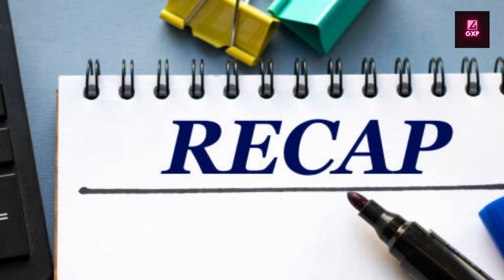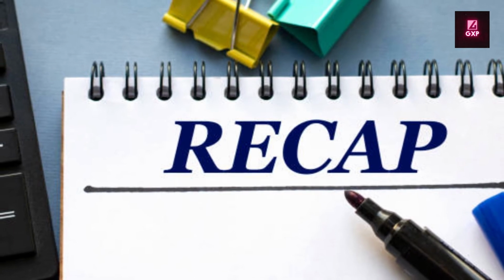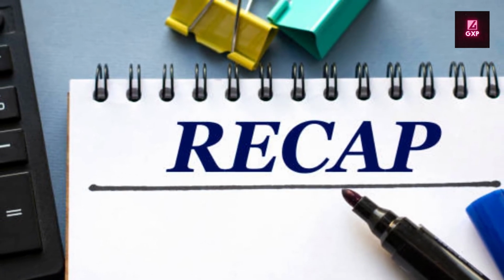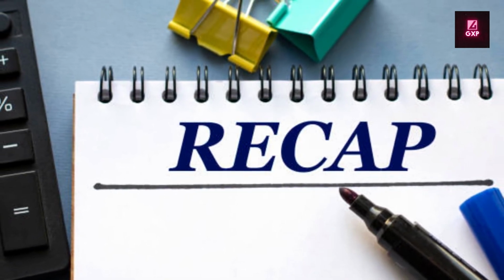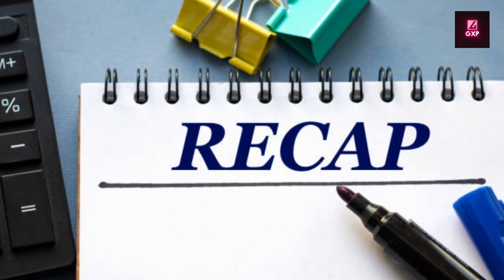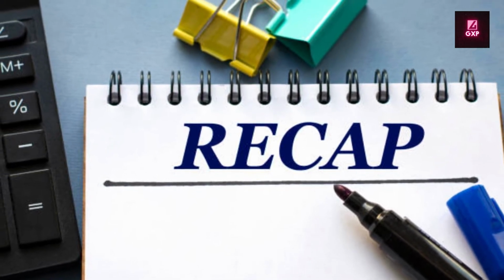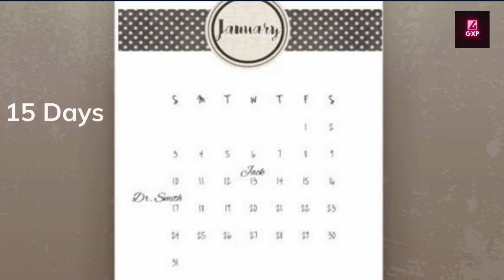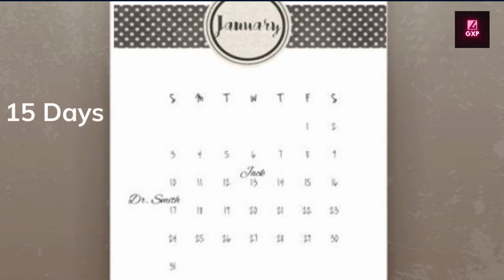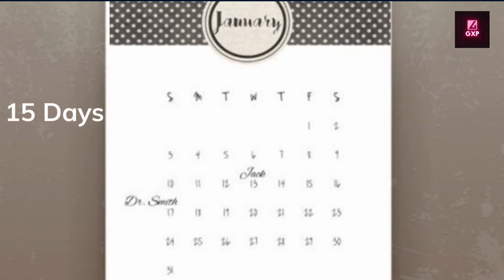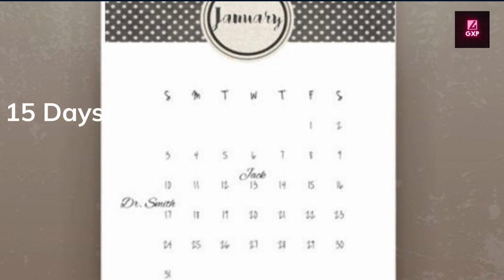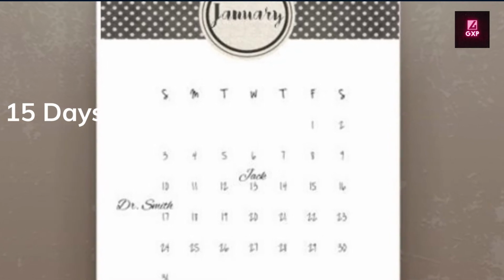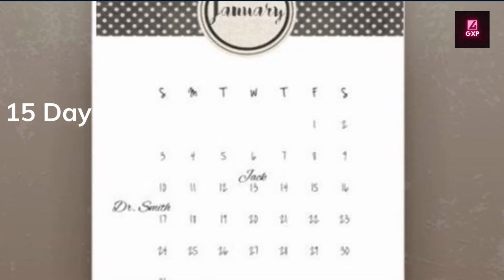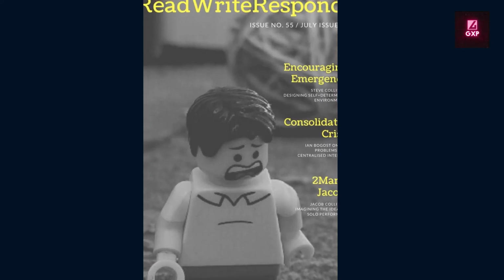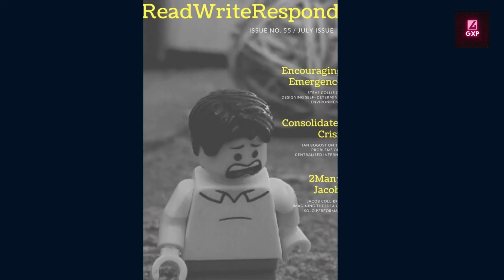Let's recap. An FDA 483 observation is a notice that highlights potential regulatory problems, while a warning letter is an escalation of this notice. You need to respond in writing within 15 days of receiving both a 483 and a warning letter. You're not obligated to handle observations cited by inspectors in a Form 483. However, it is inadvisable not to. You're far more likely to receive a warning letter if you don't address the FDA's concerns in the 483 observation.